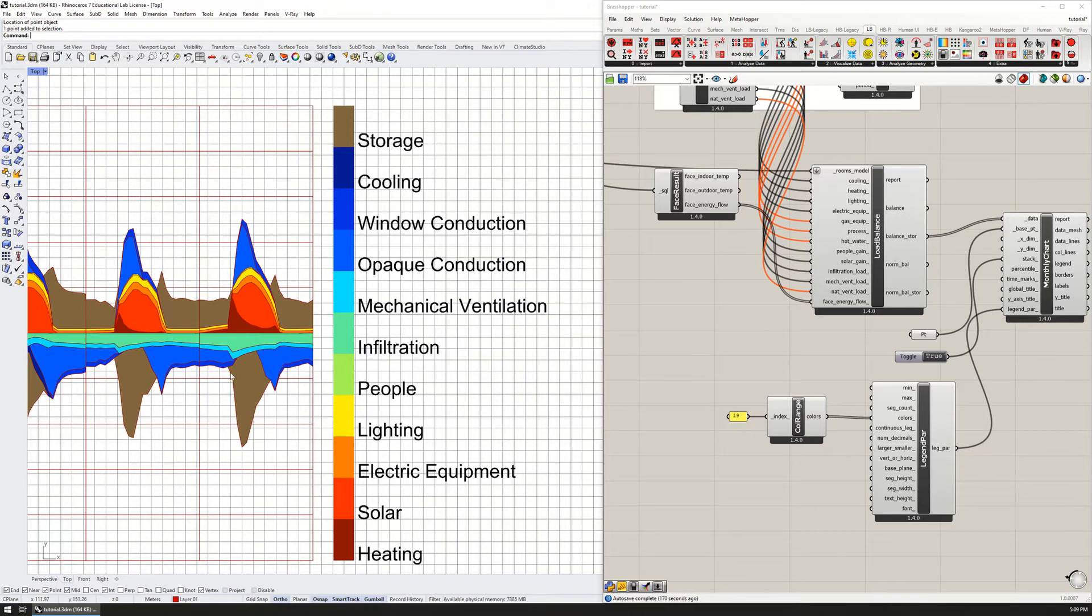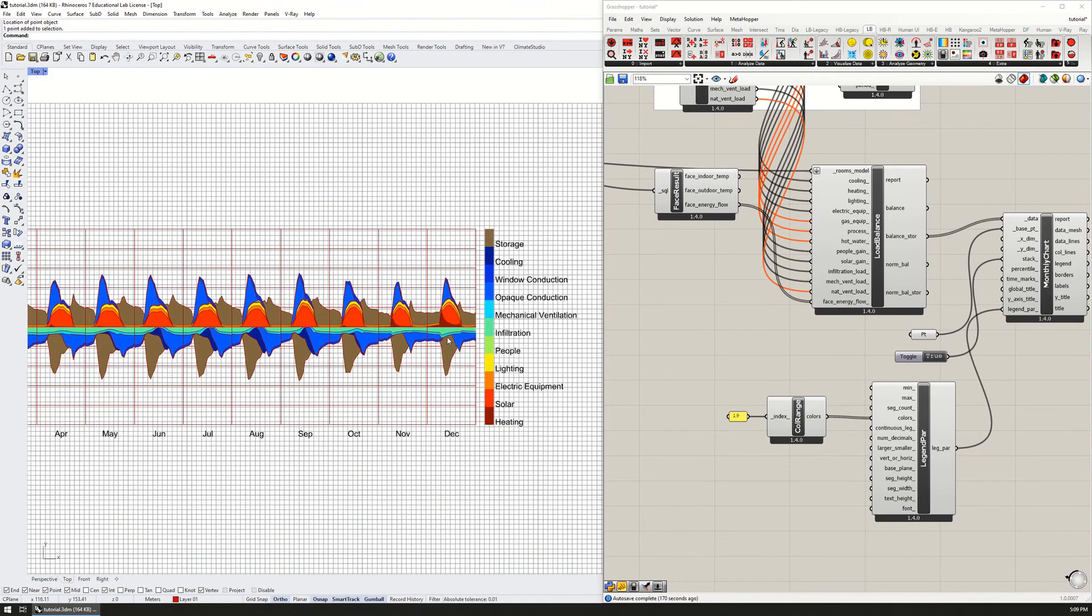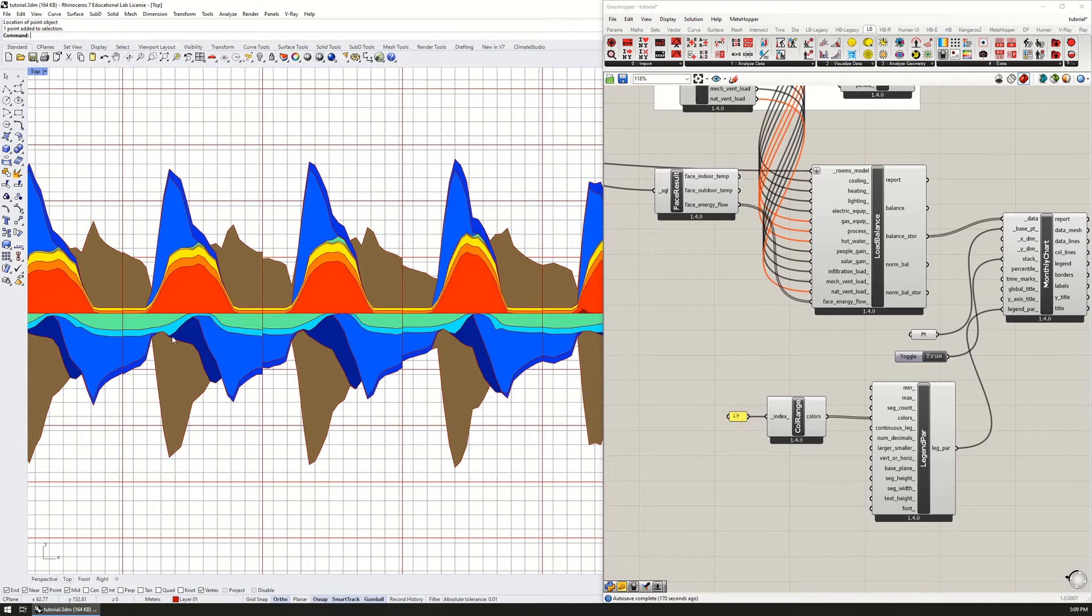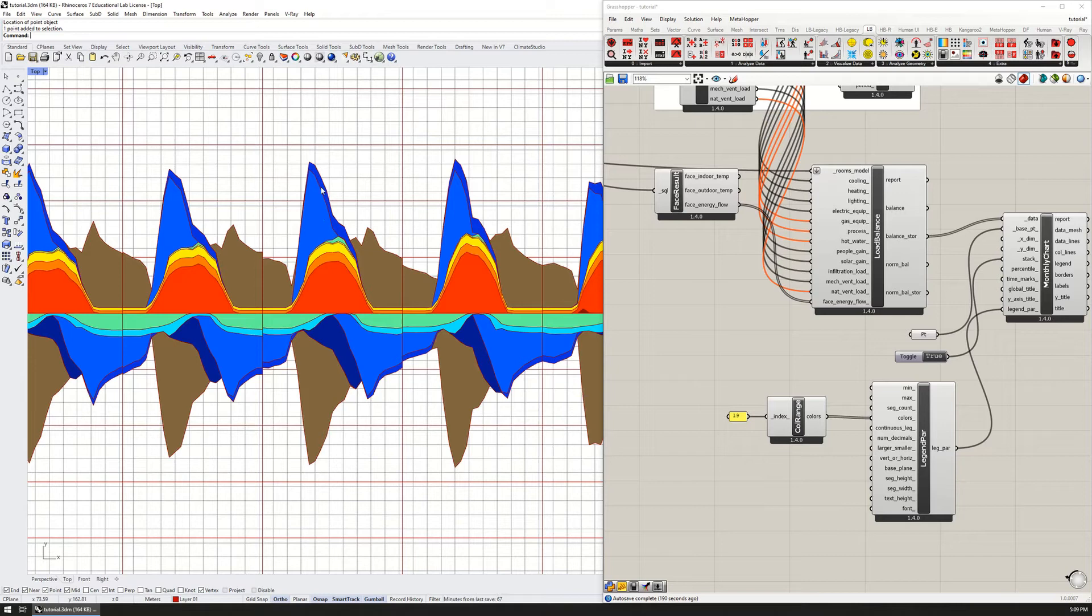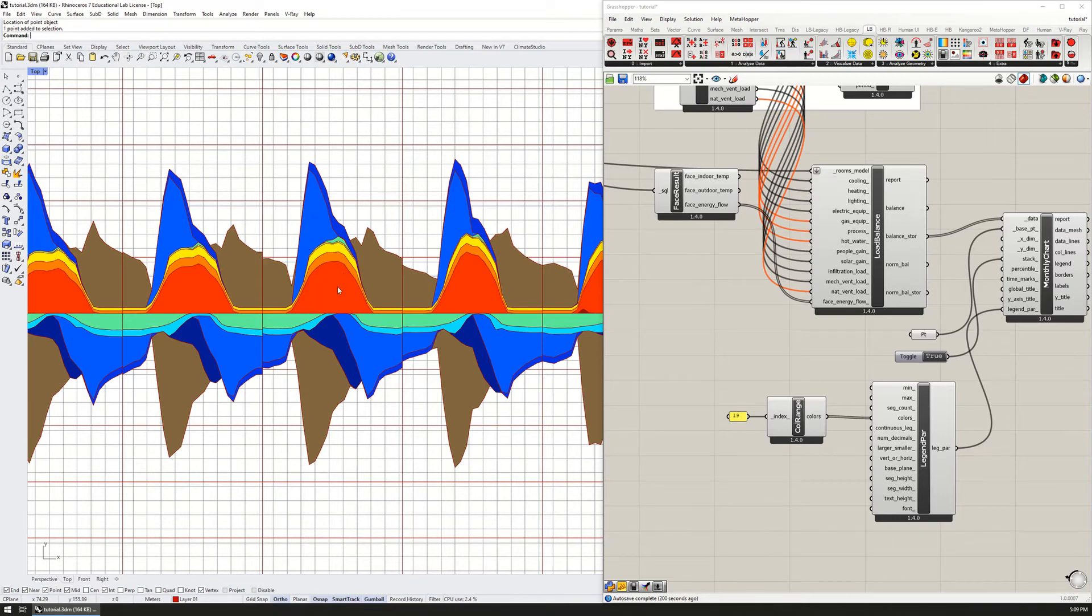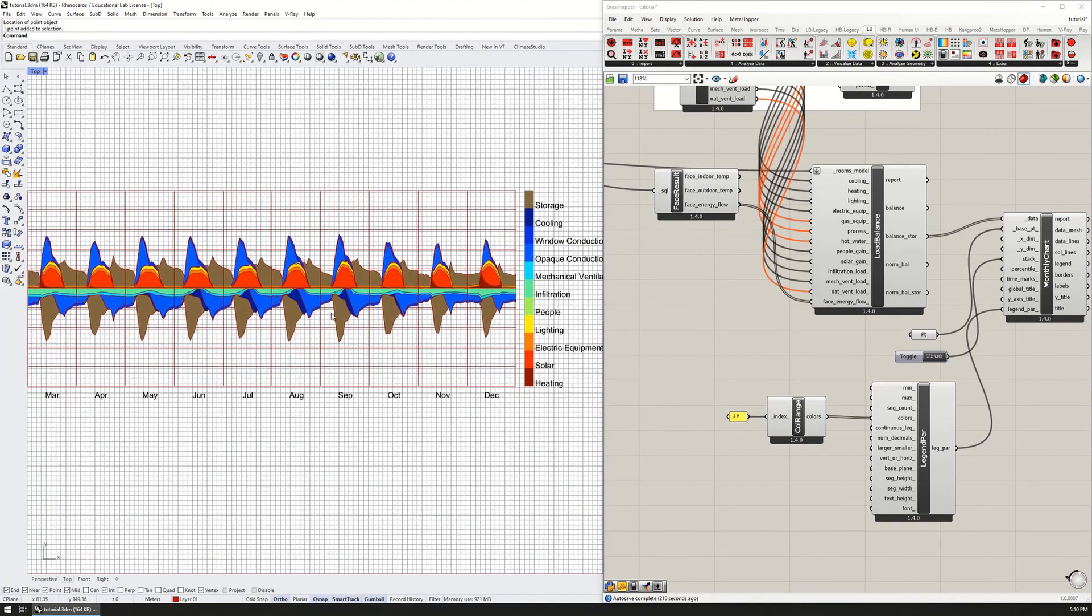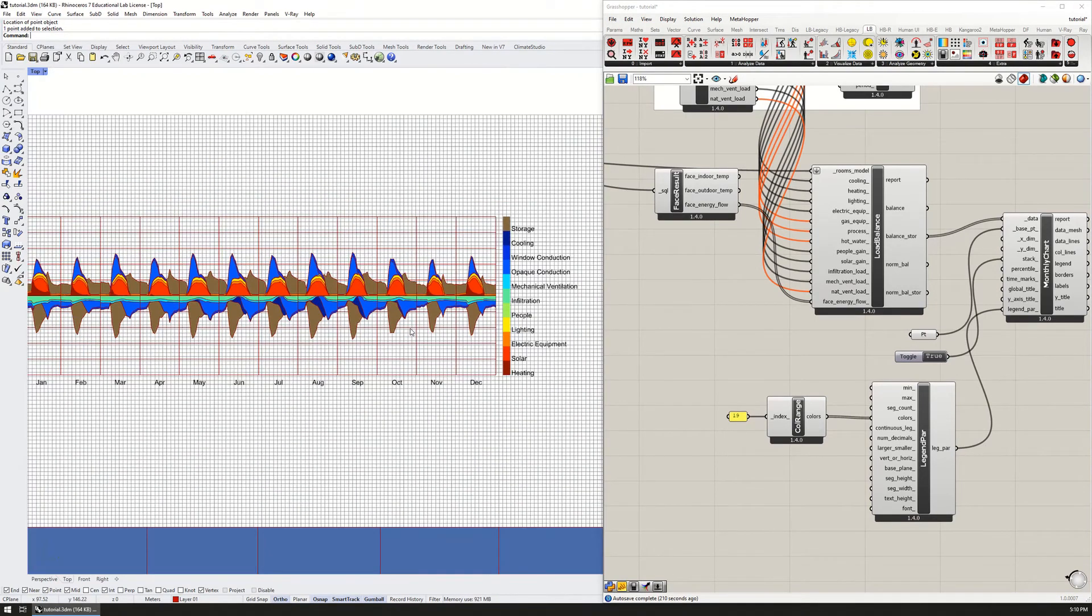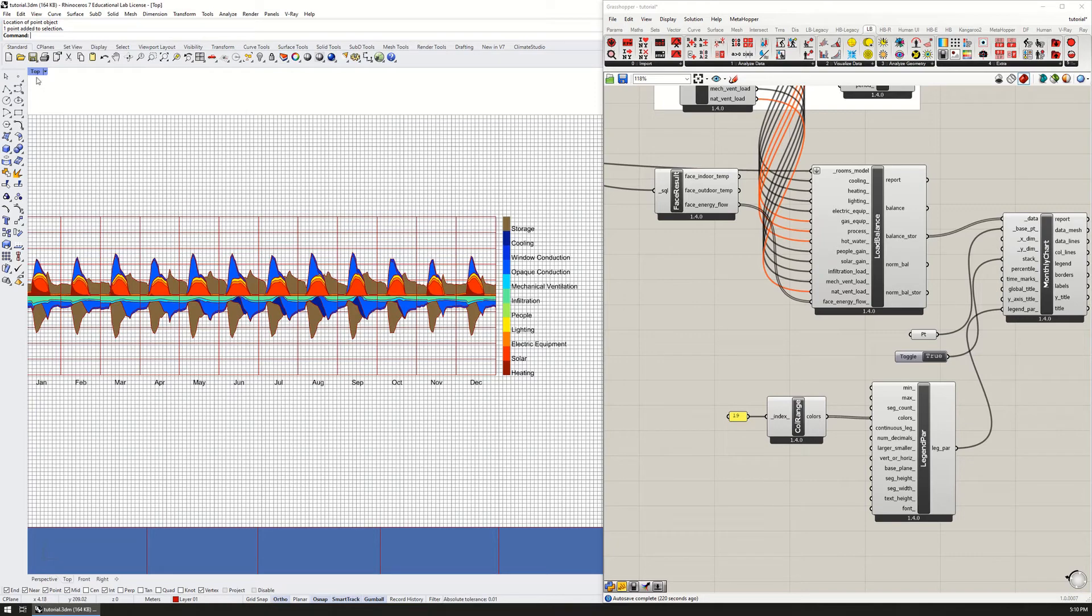The window conduction we can address by either reducing the size of windows or decreasing the u-value, increasing the thermal resistance of those windows. If we go down to the summer, you can see that the cooling is predominant right in here. The way to reduce that would be to reduce the solar load - we've got a lot of solar load here. We also have some opaque conduction and less window conduction. So again, the insulation and or thermal mass here could help, and then the shading, the windows, maybe the SHGC of the windows, maybe even smaller windows would help. It's just a way to sort of guide your work. Make sure to look at the summer as well as the winter.